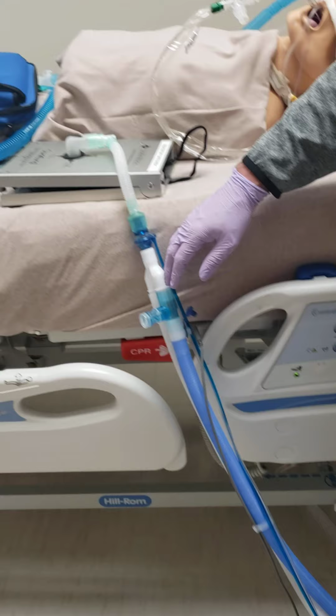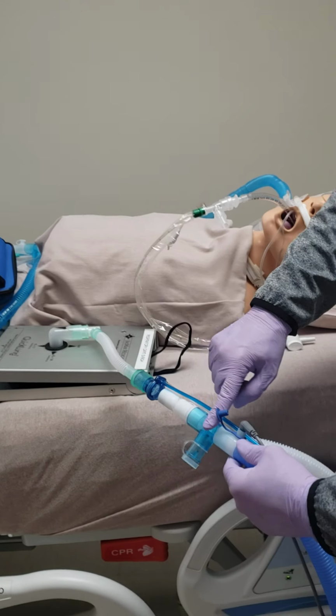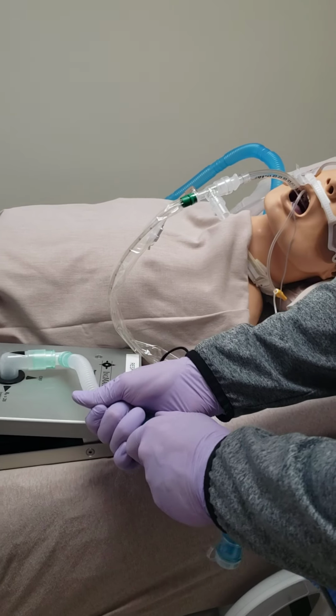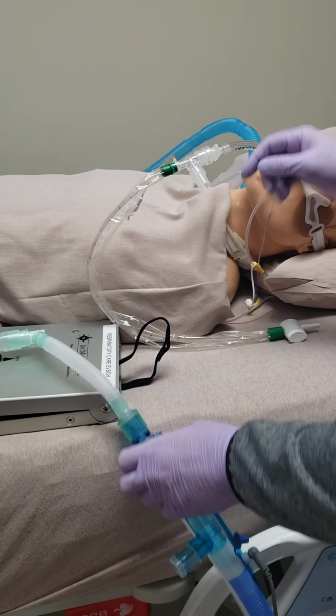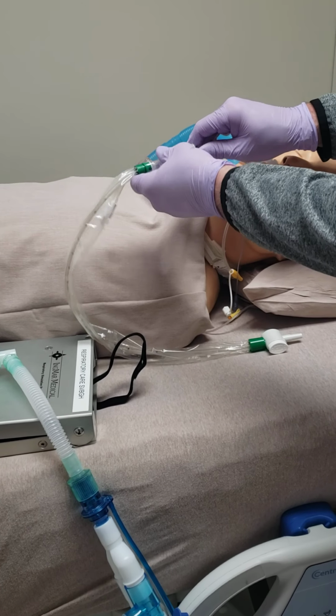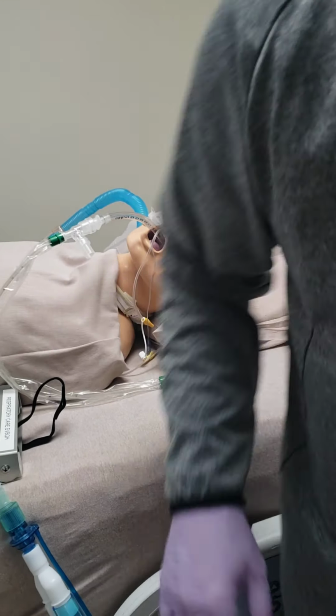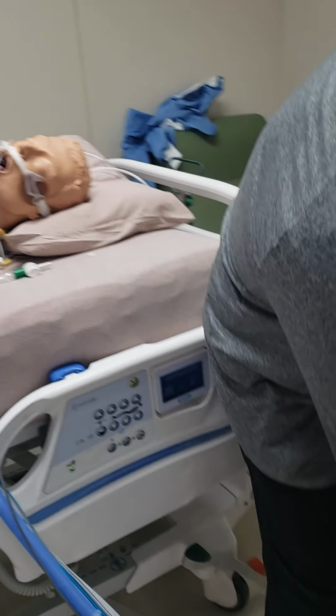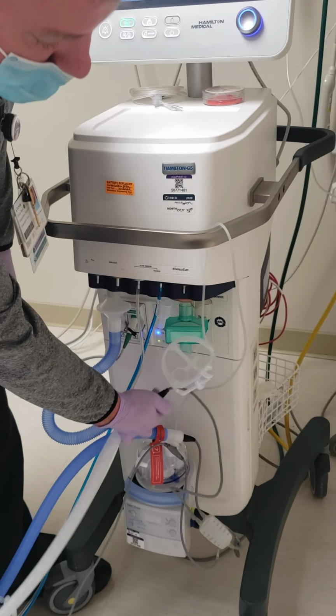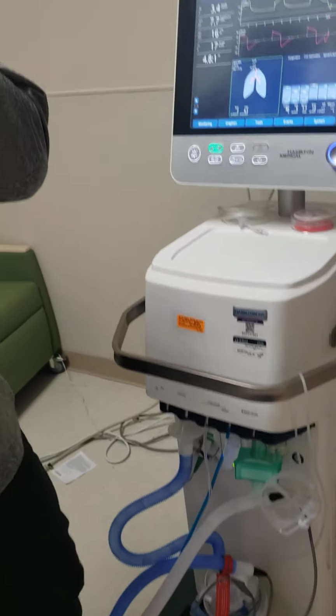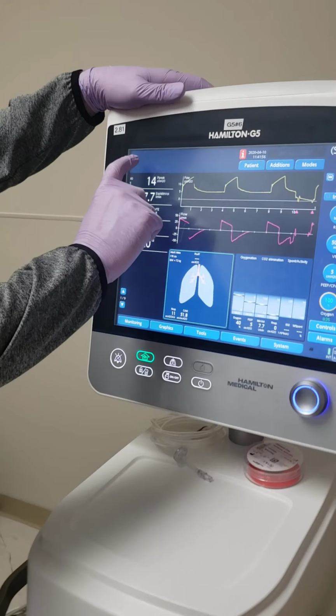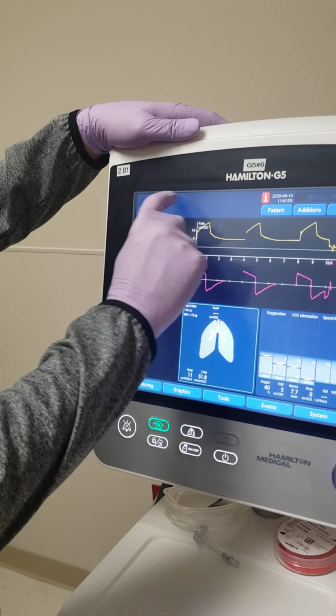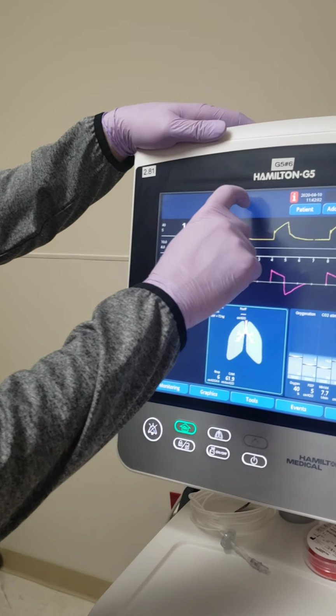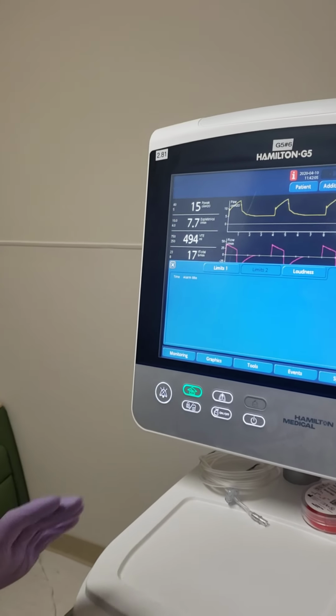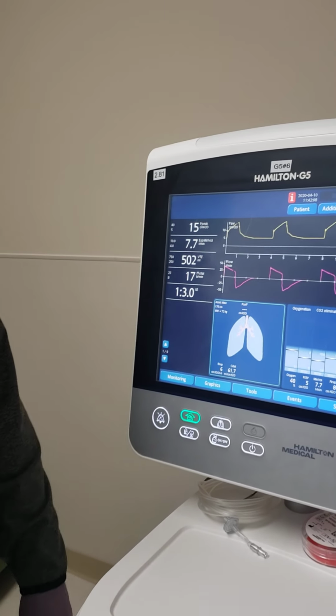Follow your circuit. Connected, connected. Sometimes they've straight up become disconnected. Sometimes they've popped off right here. It just depends. You just got to follow your circuit and find it. If you follow all the way from the vent, all the way to your patient, and you don't see it, continue on. Follow down your expiratory limb. Maybe this fell off. Okay? So you're going to see low loss of PEEP, low tidal volume, disconnection, ventilator side, patient side. Either way, you need to start looking for a disconnect somewhere. That's really the major one you need to know.